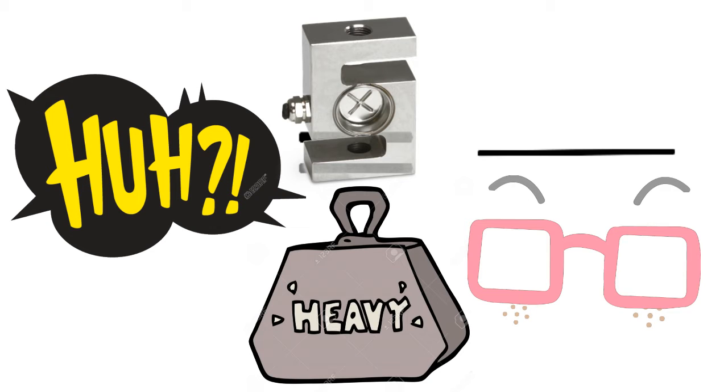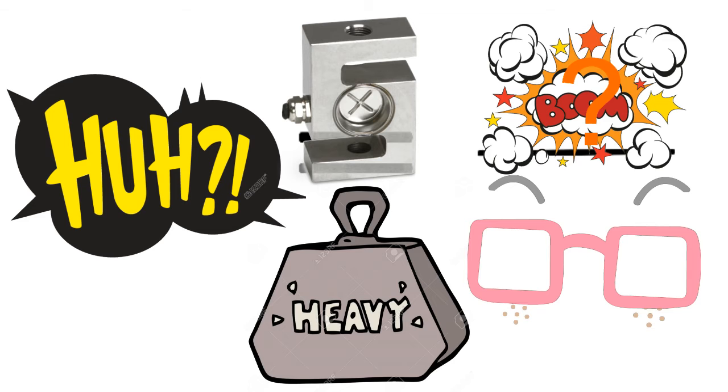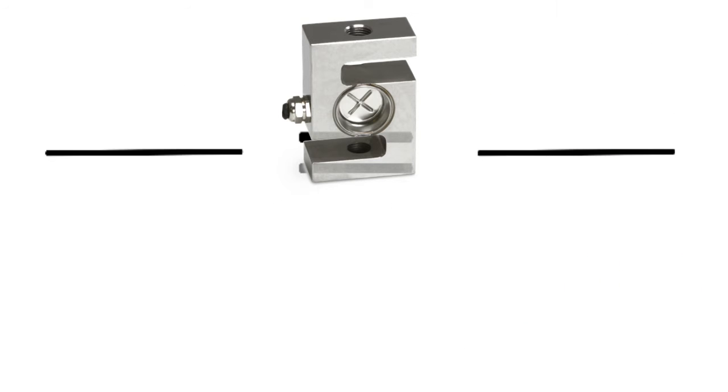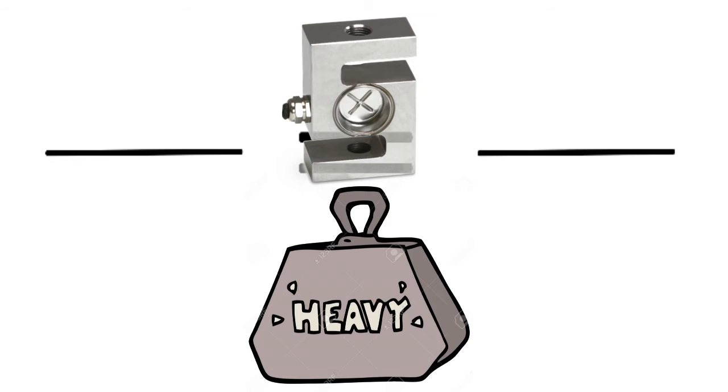How do we figure out the weight on a load cell without calibration or using a weight indicator? Every load cell has a capacity and a millivolt per volt output. Capacity is the rated load that can be placed on the load cell. The safe load capacity of a load cell is typically 150% of the rated load cell capacity.